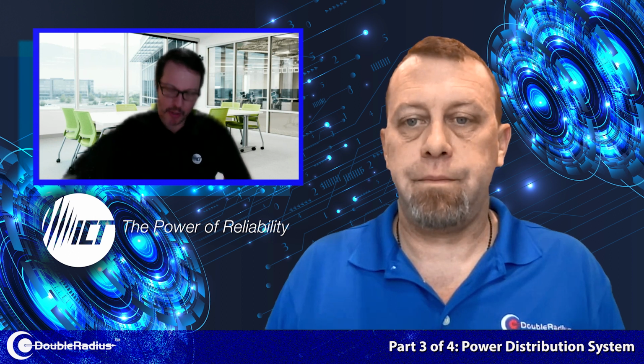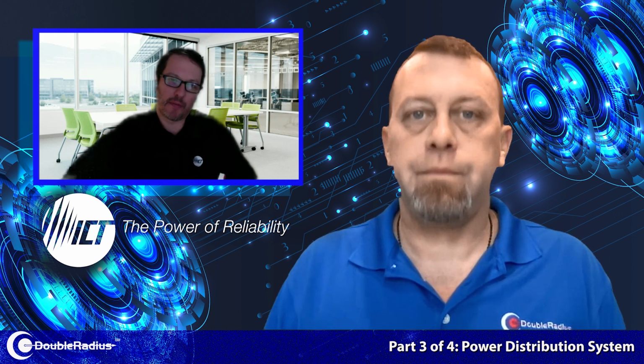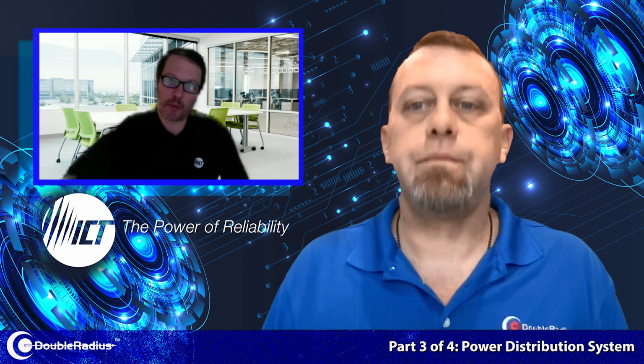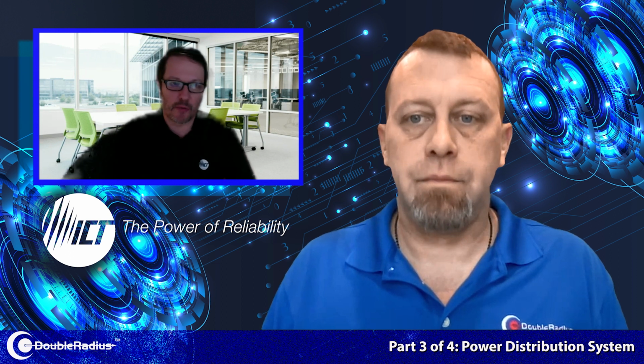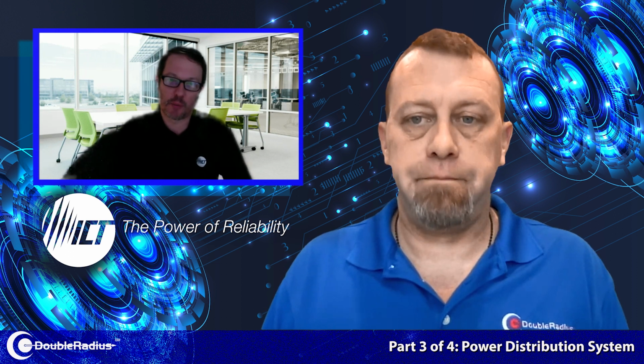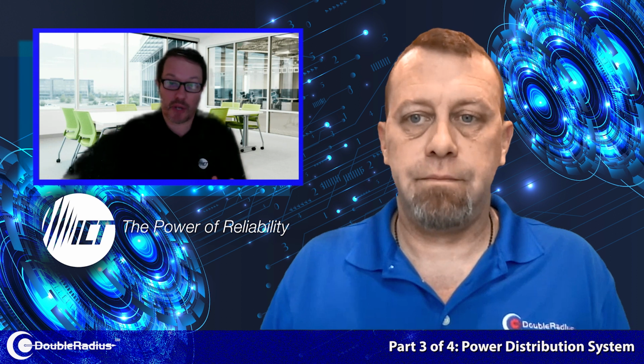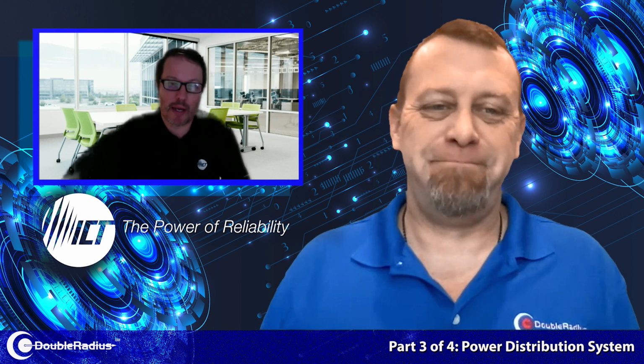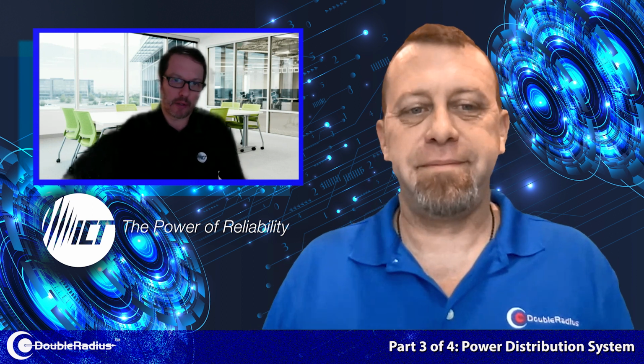On the dual bus ones, we have a 12 output, which is 6 outputs for bus A and 6 outputs for bus B. So again, you could have 6 outputs dedicated to 48, 6 to 24. Some customers use our dual bus and just connect 48 volts on both sides. You can use it that way, and they are provided 12 outputs.